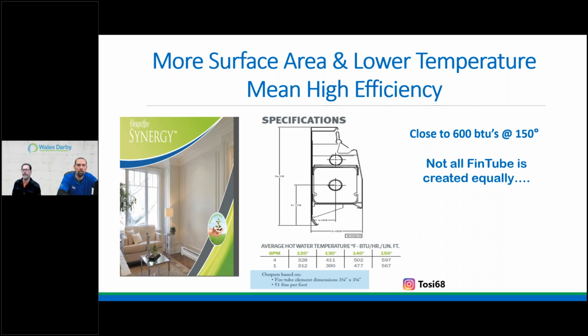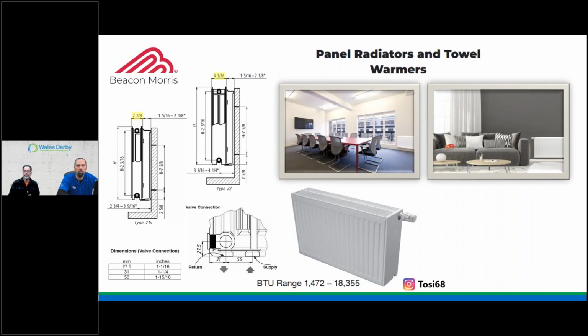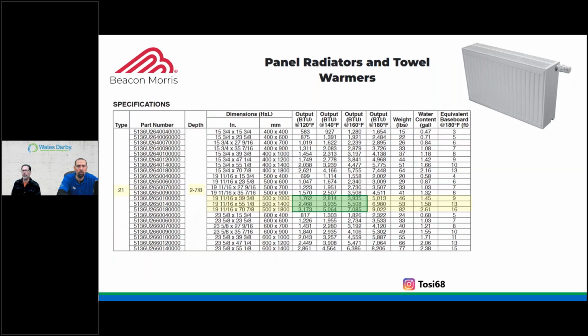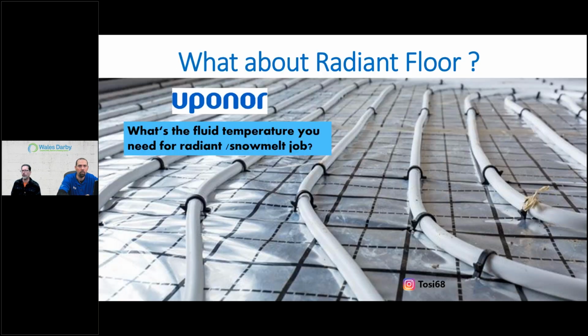All right, so again, lowering water temperature, marrying it with a high efficiency condensing piece of equipment like a boiler, 130 and less is where we want to start. So marry your emitters to that water temperature, achieve your BTUs required by your heat loss, way ahead of the game. Panel radiators, been around us. Again, it's all about surface area. Charts here showing low water temperatures, big outputs of BTUs. Again, do it all day with radiant, more surface area. Think about the whole floor becomes the emitter. Therefore, low water temperature, right?